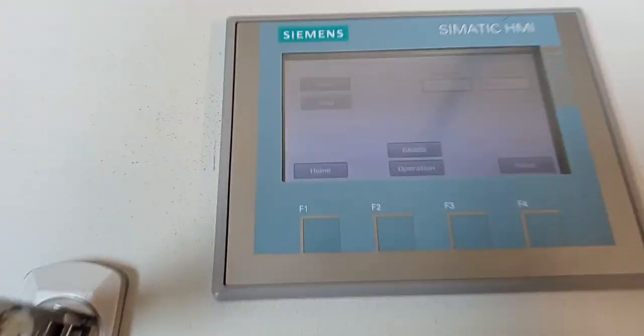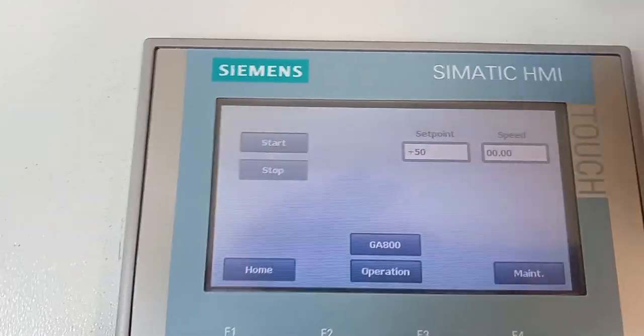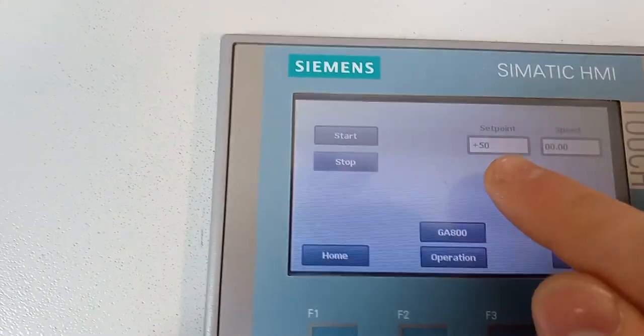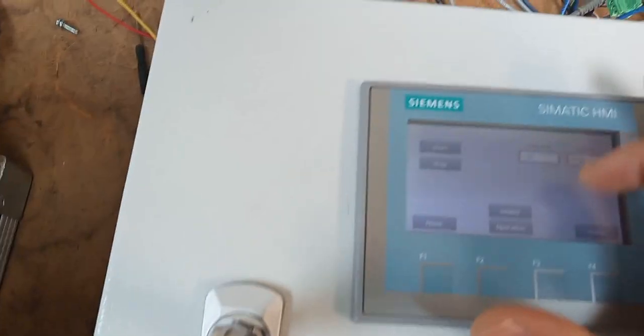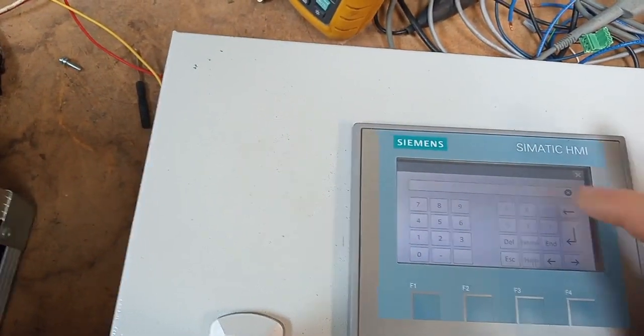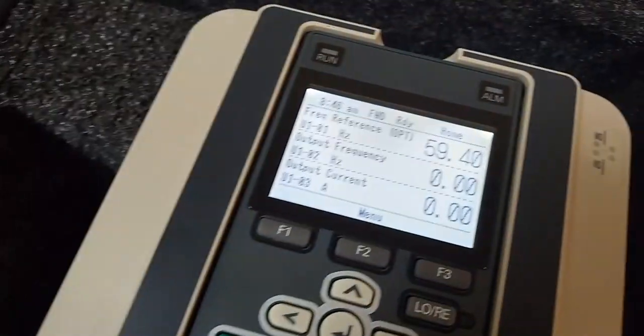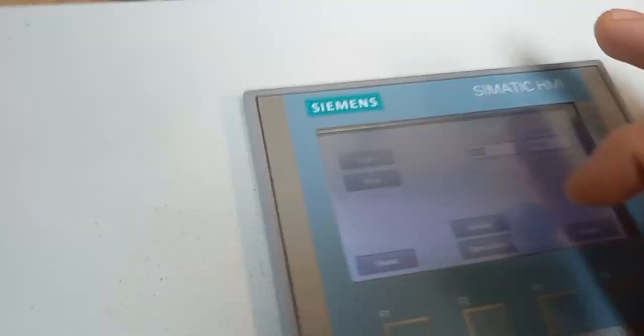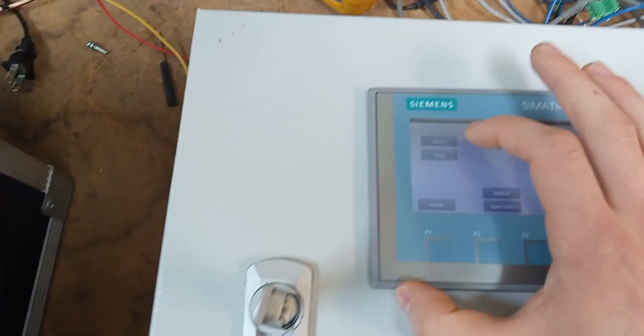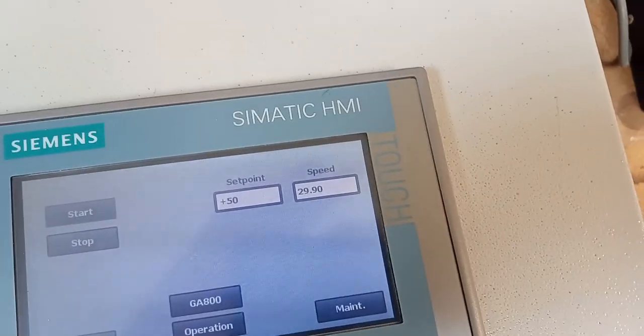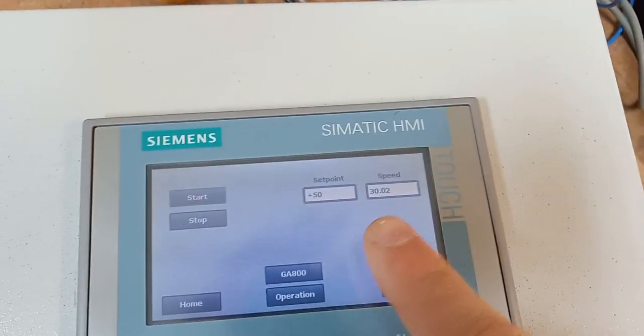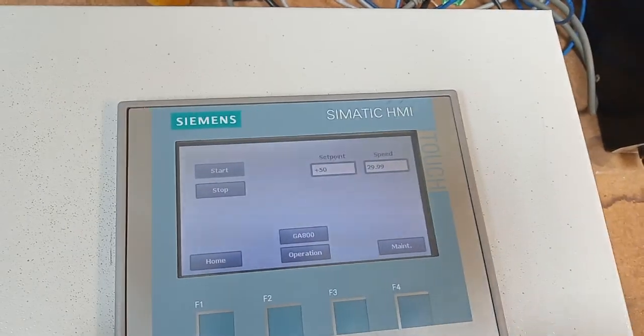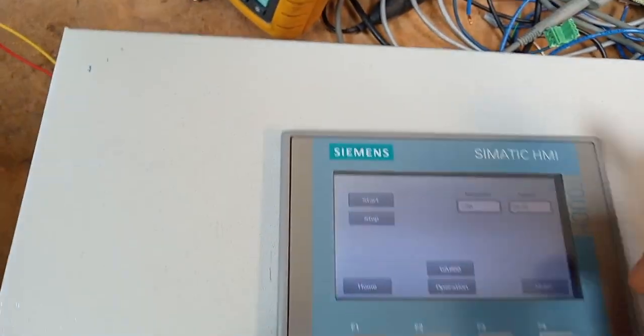So here you've got to start, stop, set point, and output speed. So 50% speed translates to 30 Hz. If I go to, let's go with, oh, let me do 100, go to 99. 99 is going to be about 60 Hz. It's the maximum speed. Let's go ahead and bring that on back down to 50% speed. Now when I hit the start button over here, there she goes. Starts ramping up. My little output dialer right there. It's going to tell me the actual speed that it's running at. Isn't it fun for operators or maintenance personnel or whoever to see that.